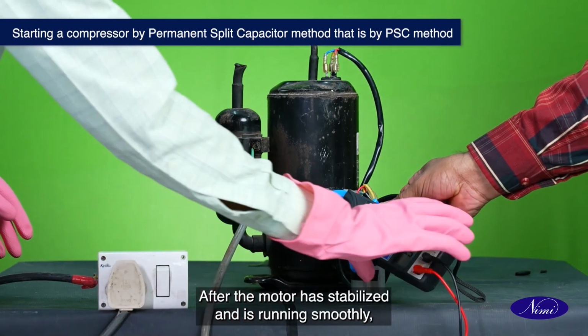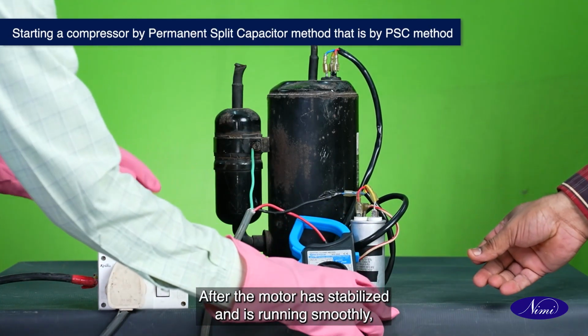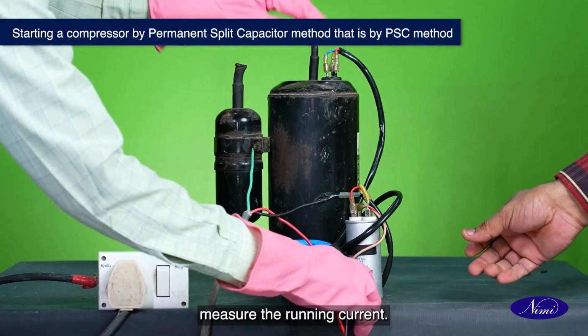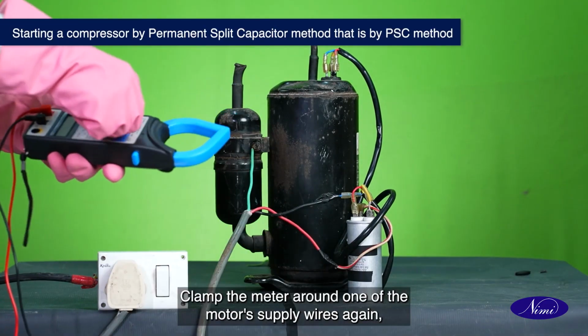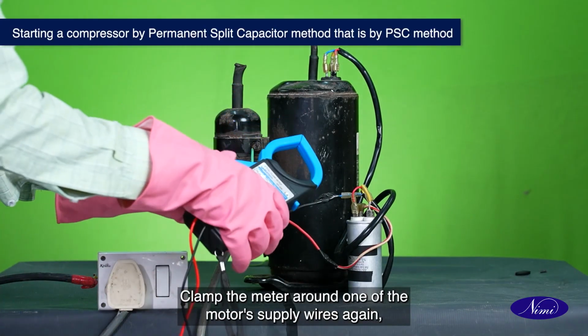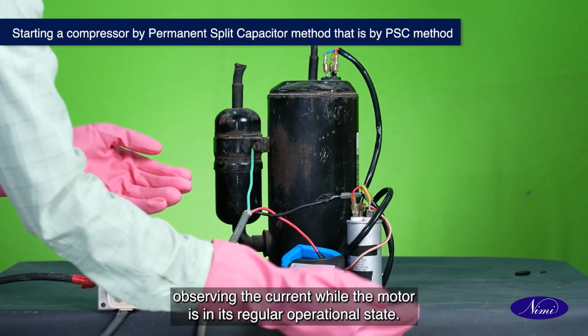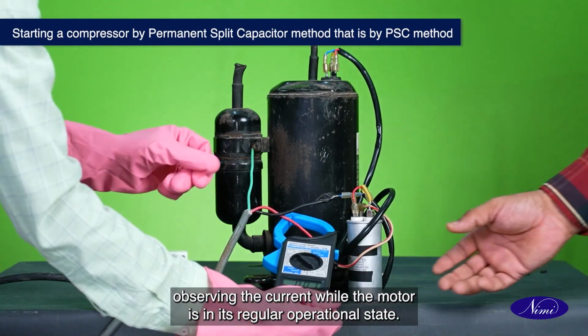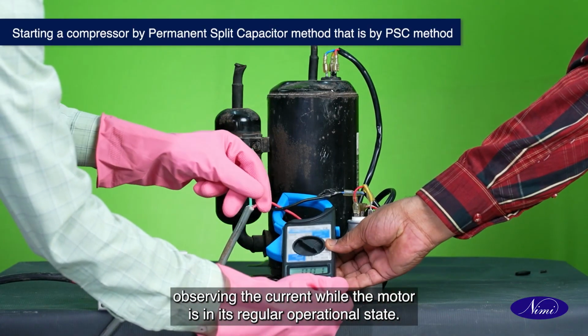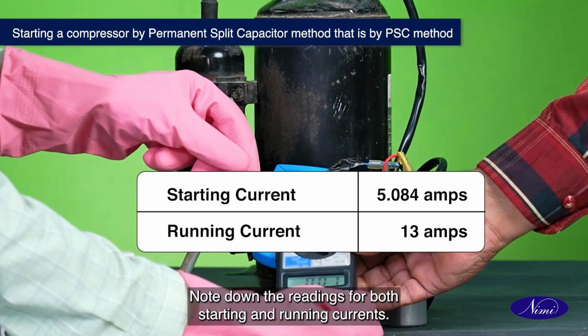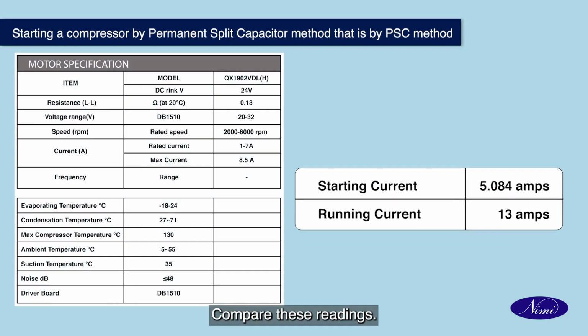After the motor has stabilized and is running smoothly, measure the running current. Clamp the meter around one of the motor's supply wires again, observing the current while the motor is in its regular operational state. Note down the readings for both starting and running currents. Compare these readings against the motor's specifications or recommended values.